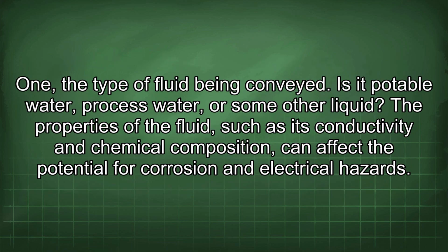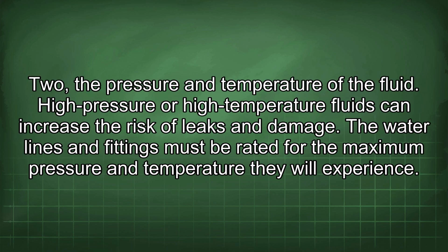1. The type of fluid being conveyed. Is it potable water, processed water, or some other liquid? The properties of the fluid, such as its conductivity and chemical composition, can affect the potential for corrosion and electrical hazards. 2. The pressure and temperature of the fluid. High pressure or high temperature fluids can increase the risk of leaks and damage. The water lines and fittings must be rated for the maximum pressure and temperature they will experience.